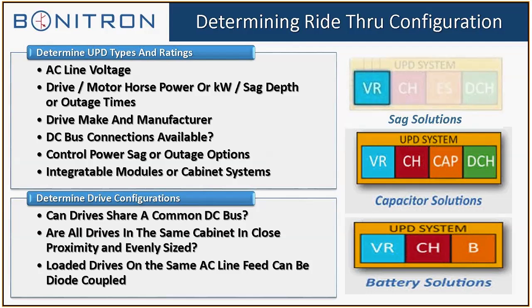Now there are other considerations where you can provide a more economical solution, and that's common busing the inverters of the drives, tying the drives together at the DC bus. The considerations here are the proximity of the drives to each other.